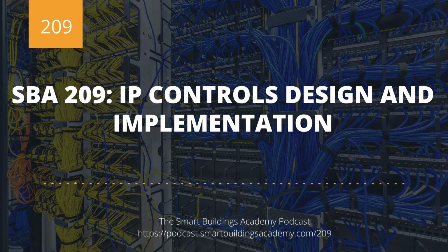Whereas in most IP controllers, they are not electrically bridged, they are bridged by software. So because of that, to go from one network interface card to the other and then send the signal out, you need the controller to be powered. Now, many manufacturers are working to rectify this so that it's independent of if the controller's powered or not, and the signal will just continue on. But right now, that is a limitation.